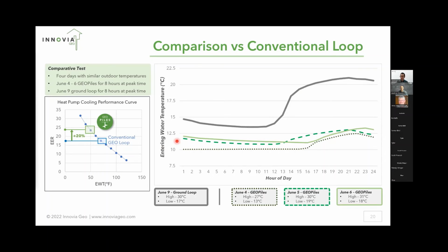Just like a power system, you have your base load generators and your peaking power plants. Right now, all our systems are designed as peaking power plants because we need to meet those peak cold days and hot days like today. But all the other times of the year, you're operating the system at part load. And so with that property and being able to use this thermal storage property, we can start, and we'll be starting testing control strategies around maybe prepping a system for a heat wave that's coming so that we're able to keep it in a more efficient range over a couple of days.